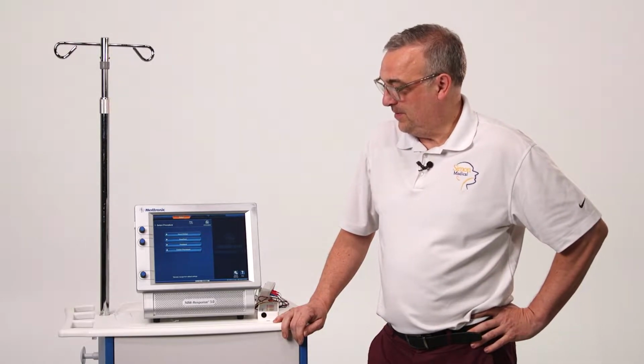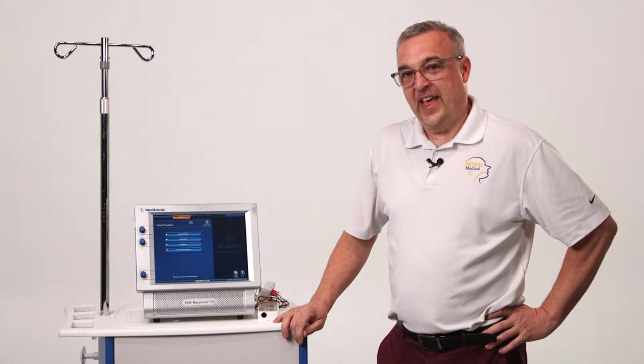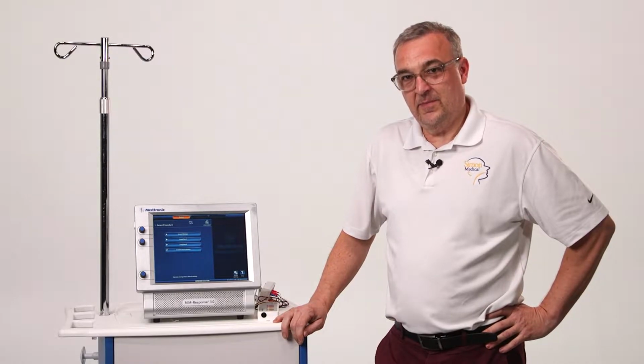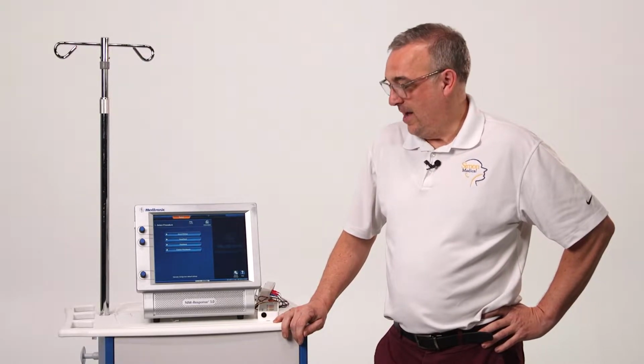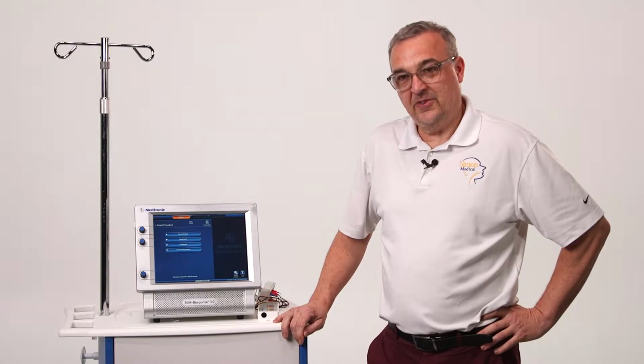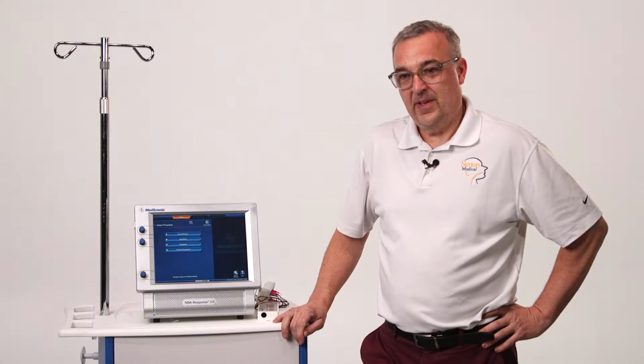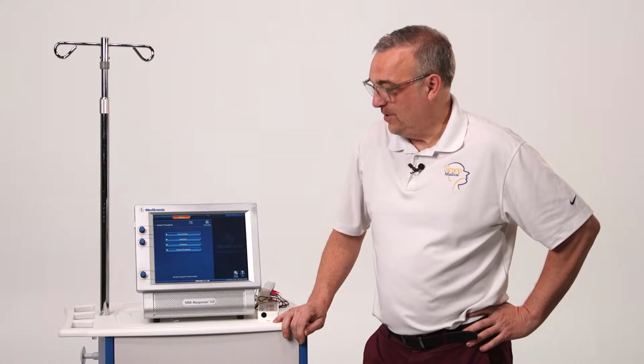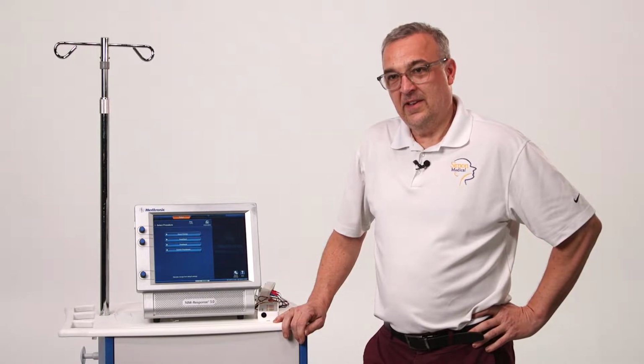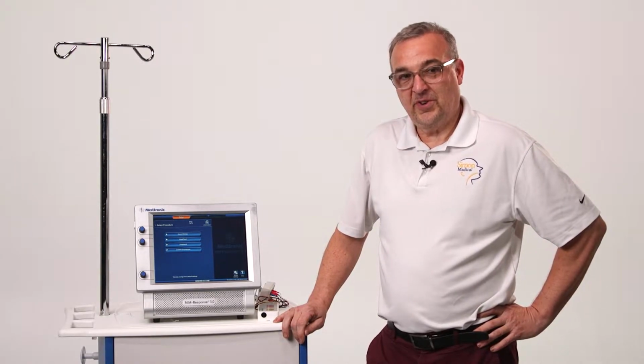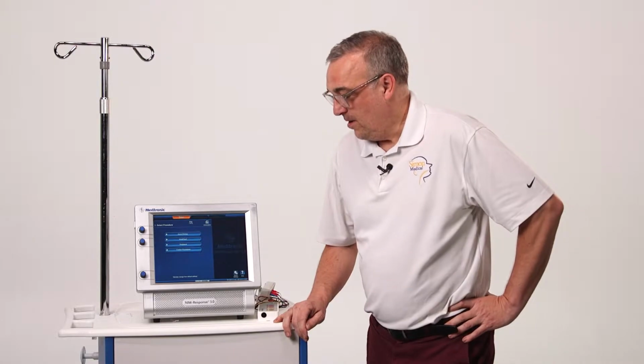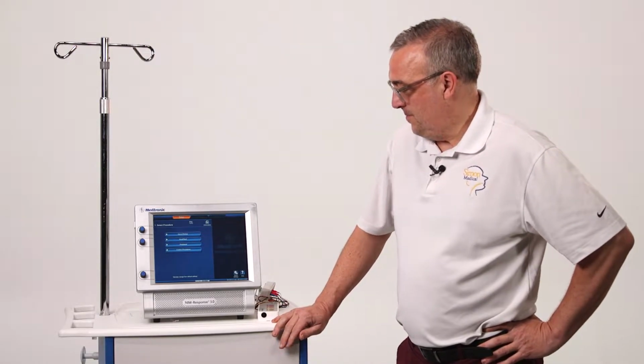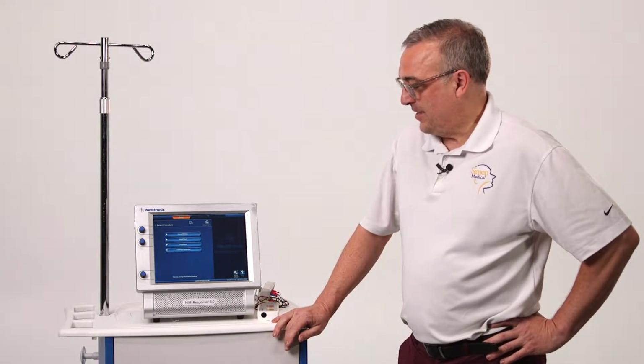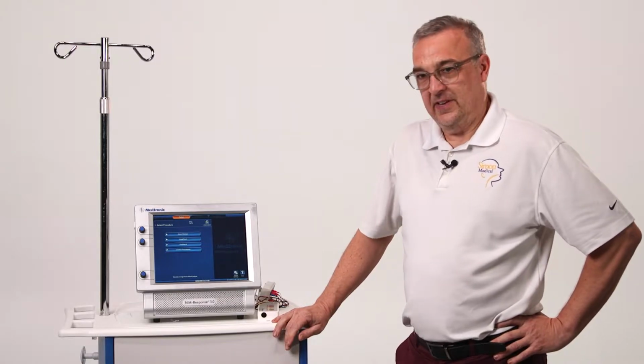What I want to do is cover basic setup once the machine's in the room and once you have the electrodes on the patient, and how to set it up, how to adjust the settings when needed, and maybe a little bit of troubleshooting.